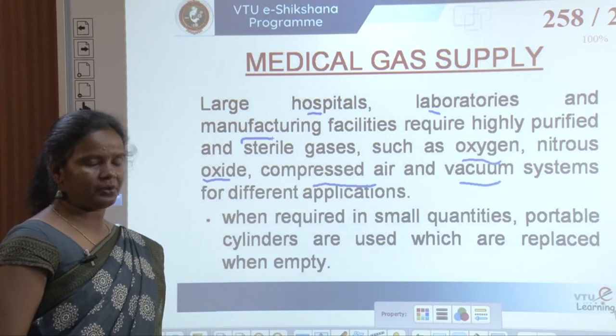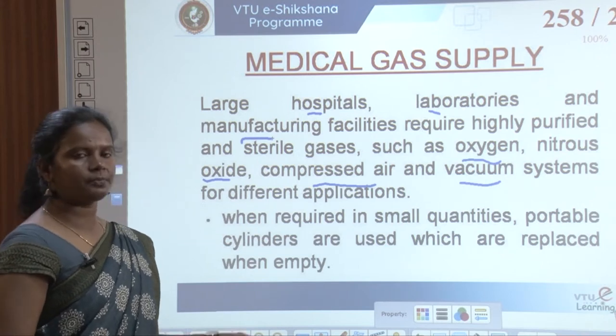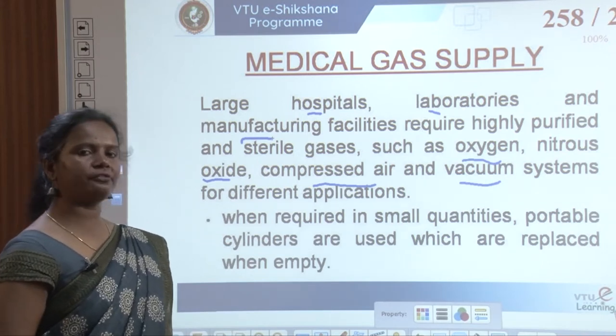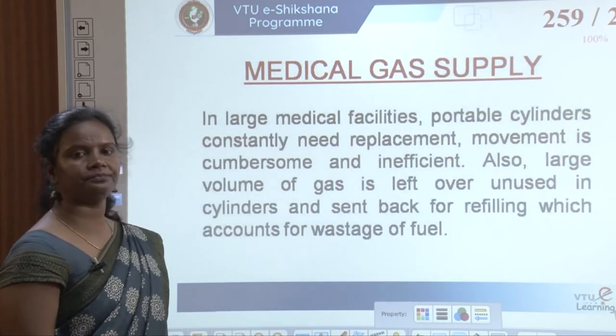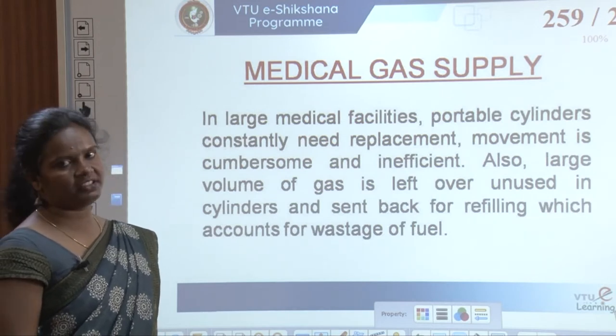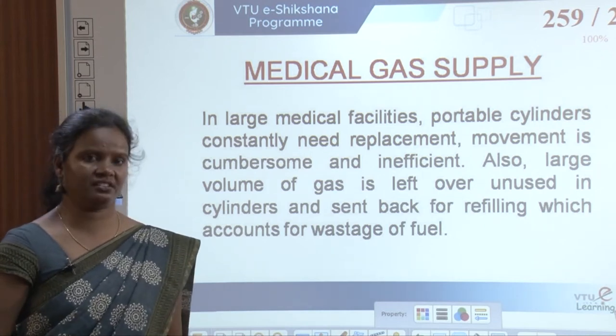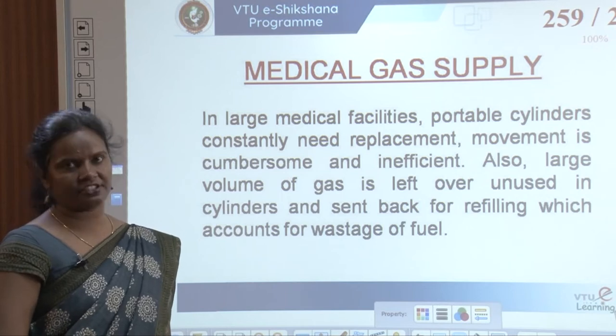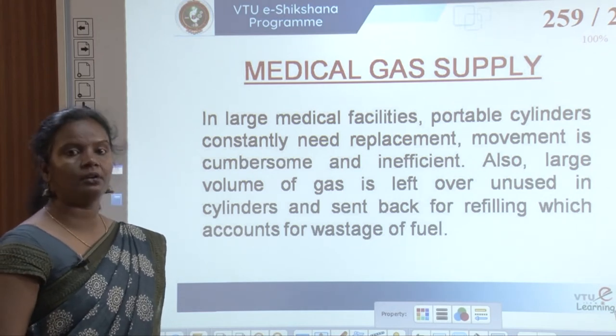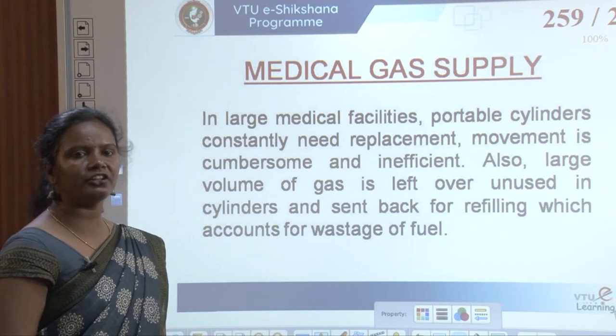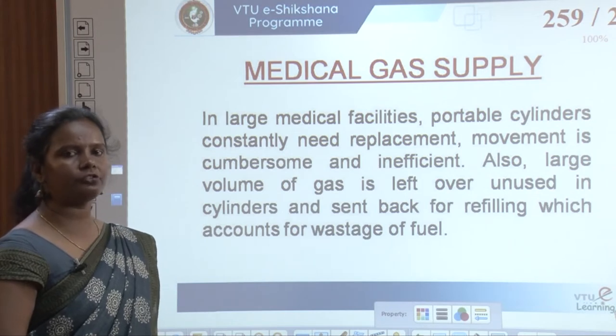When required in small quantities, portable cylinders are used and replaced when empty. However, in large medical facilities, portable cylinders constantly need replacement, which is cumbersome and inefficient. Also, large volumes of gas are left over unused in cylinders sent back for refilling, which accounts for wastage.